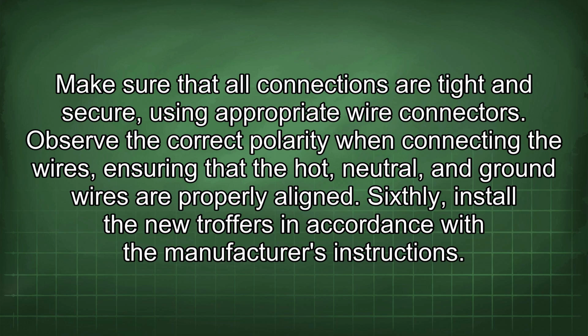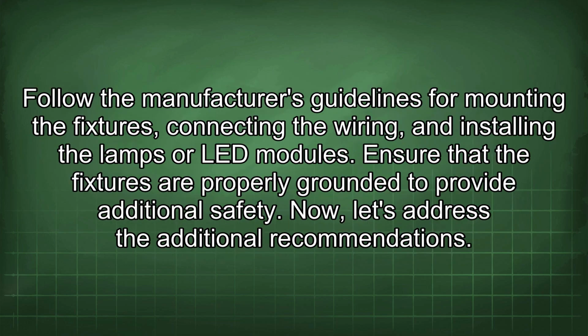Sixthly, install the new troffers in accordance with the manufacturer's instructions. Follow the manufacturer's guidelines for mounting the fixtures, connecting the wiring, and installing the lamps or LED modules. Ensure that the fixtures are properly grounded to provide additional safety.